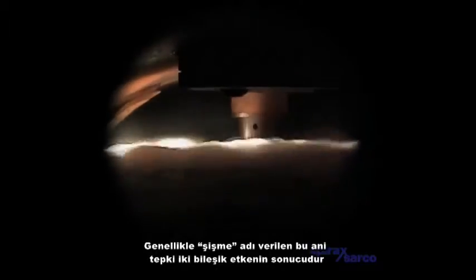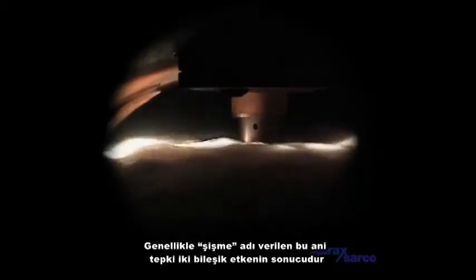This sudden response, often referred to as swell, is a result of two compounding factors. 1. The steam bubbles within the main boiler water expand under the reduced pressure, causing the surface level to rise. And 2. At the same time, water flashes to steam, resulting in more turbulence.